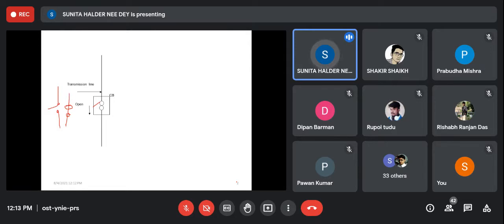So it is required to disconnect the circuit at that high current. So there must be good insulation and good current bearing copper capacity in this circuit breaker. In one word we can say it is a switch, but it is not as simple as the switch in an electrical circuit. Now who will give the information whether the circuit breaker will open or not? Who will give the information whether current is 500 ampere or 2.5 kilo ampere? That is provided by the relay.